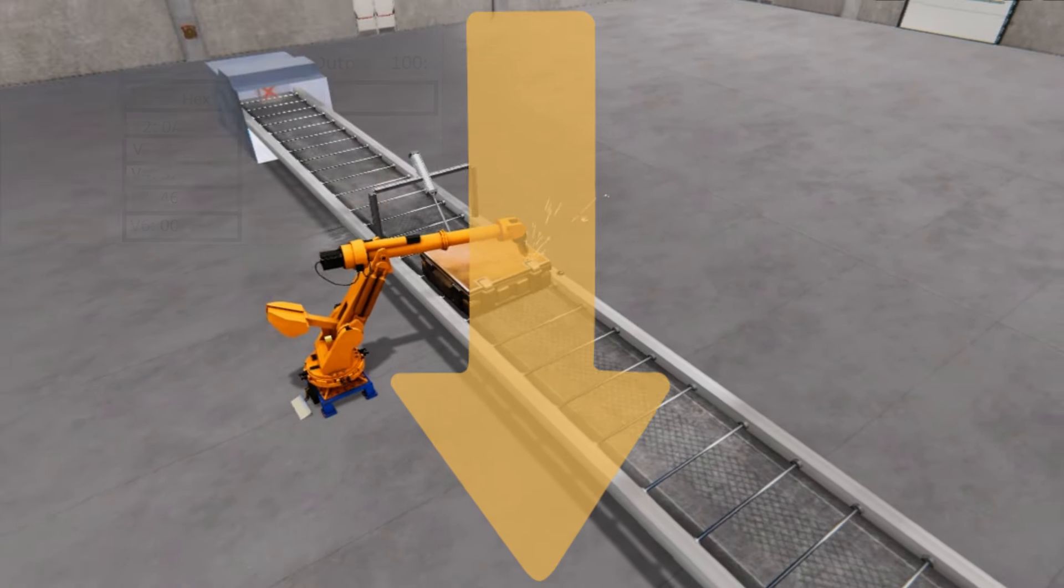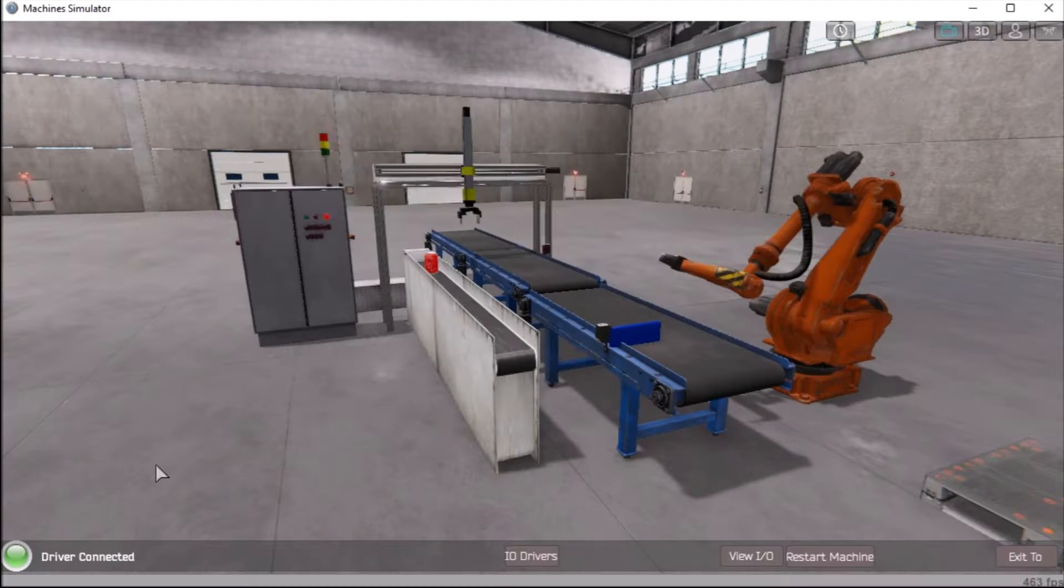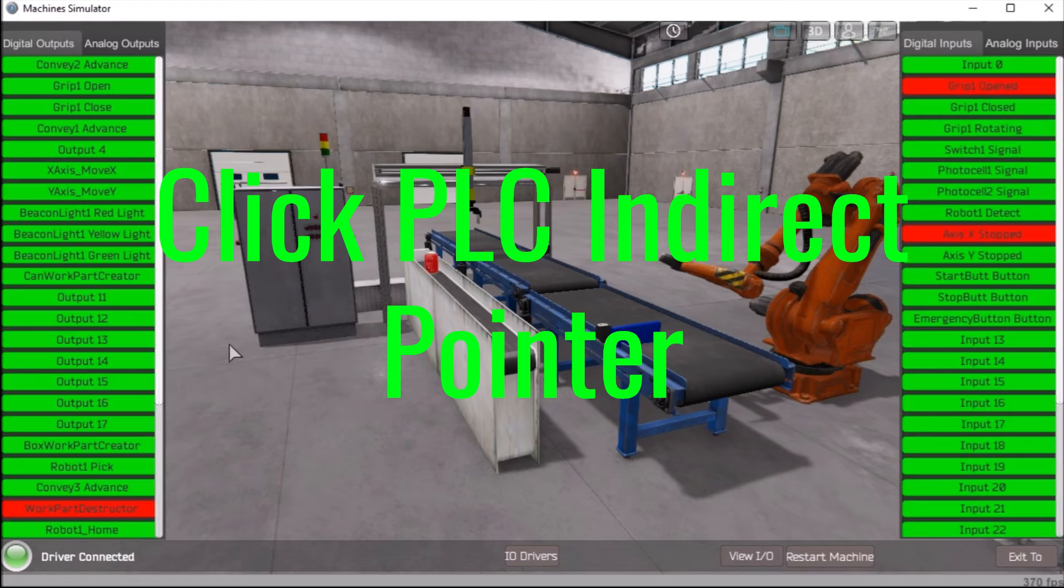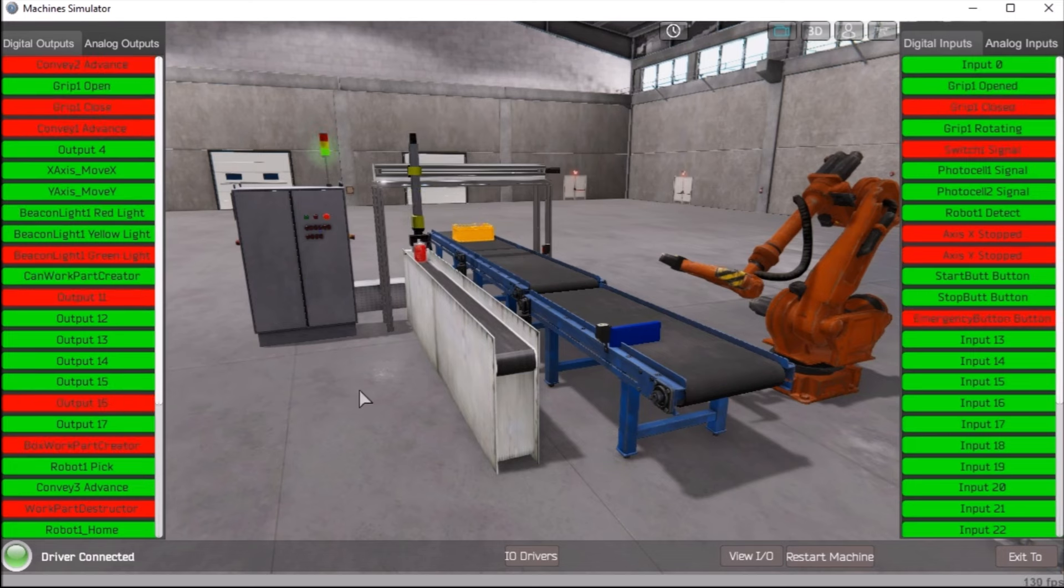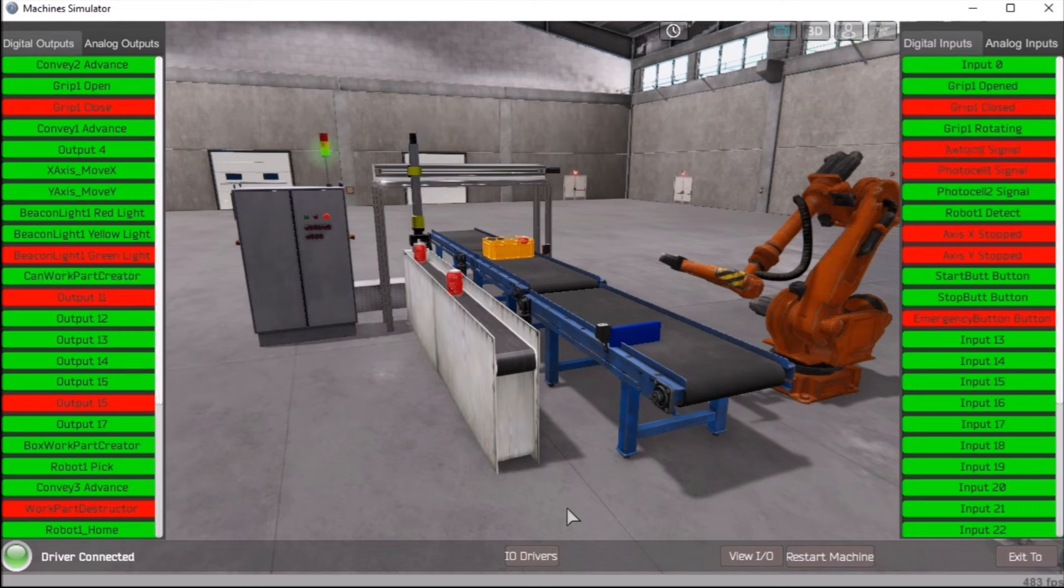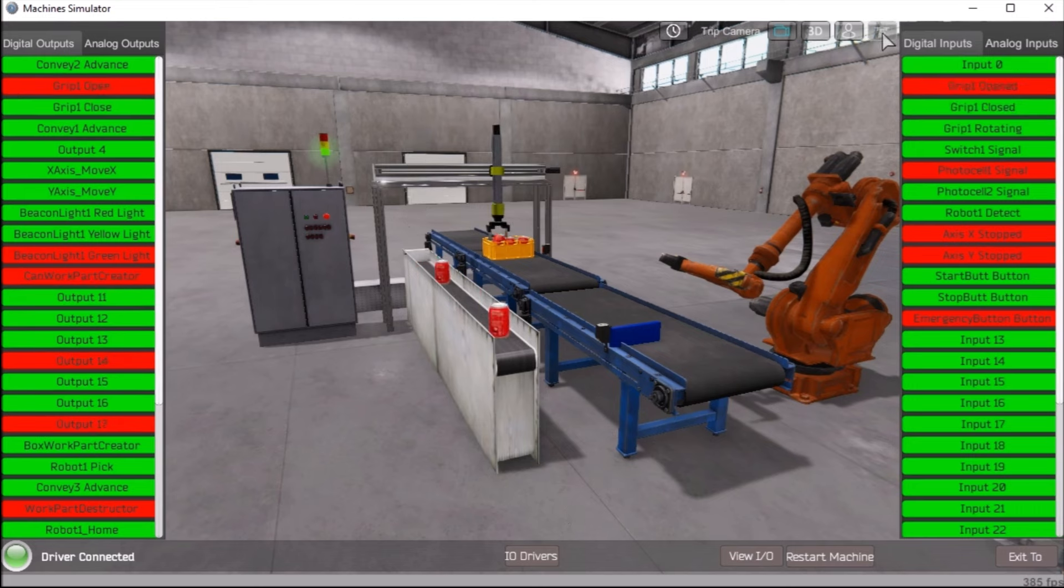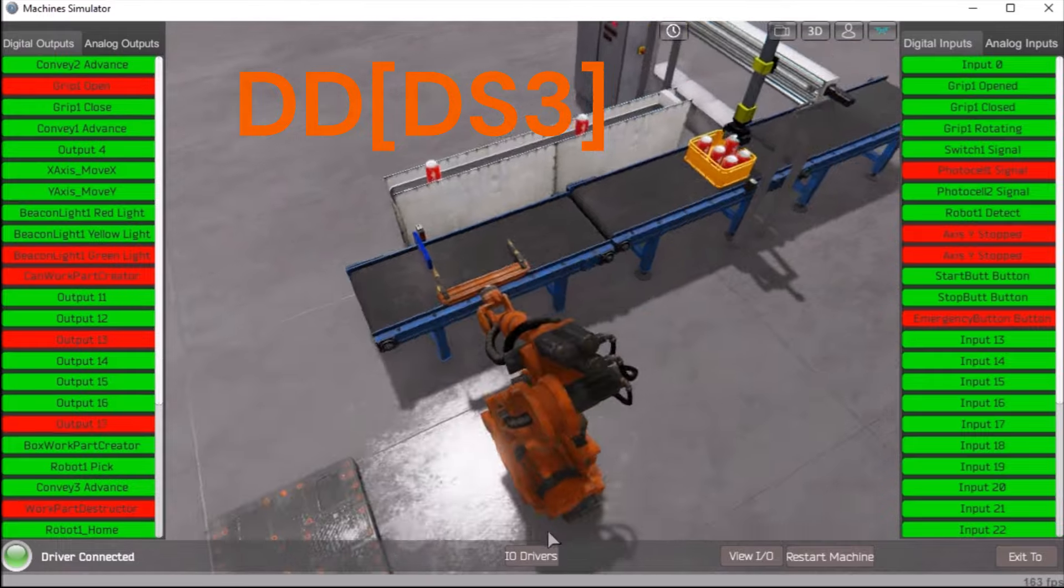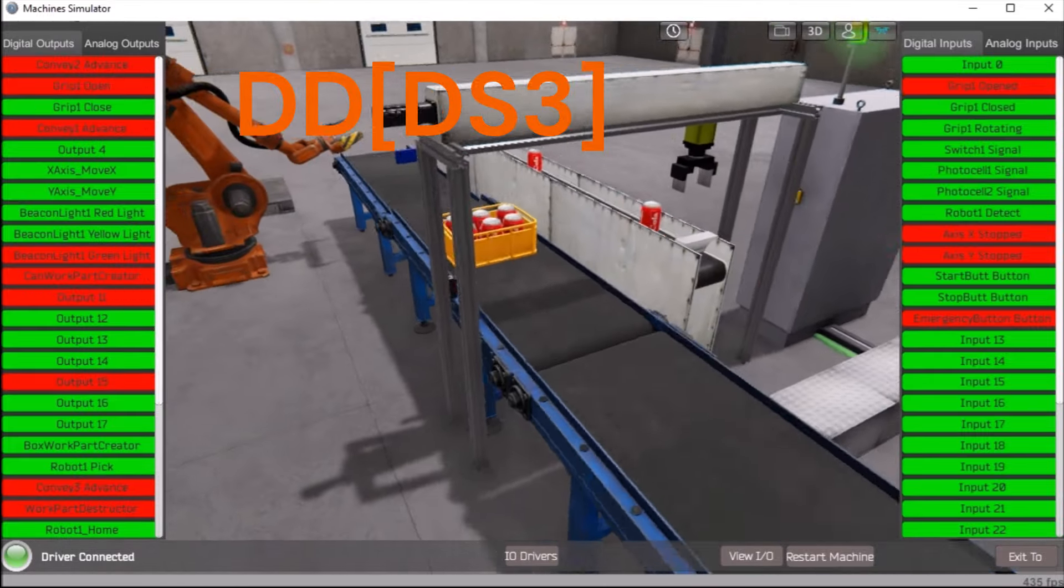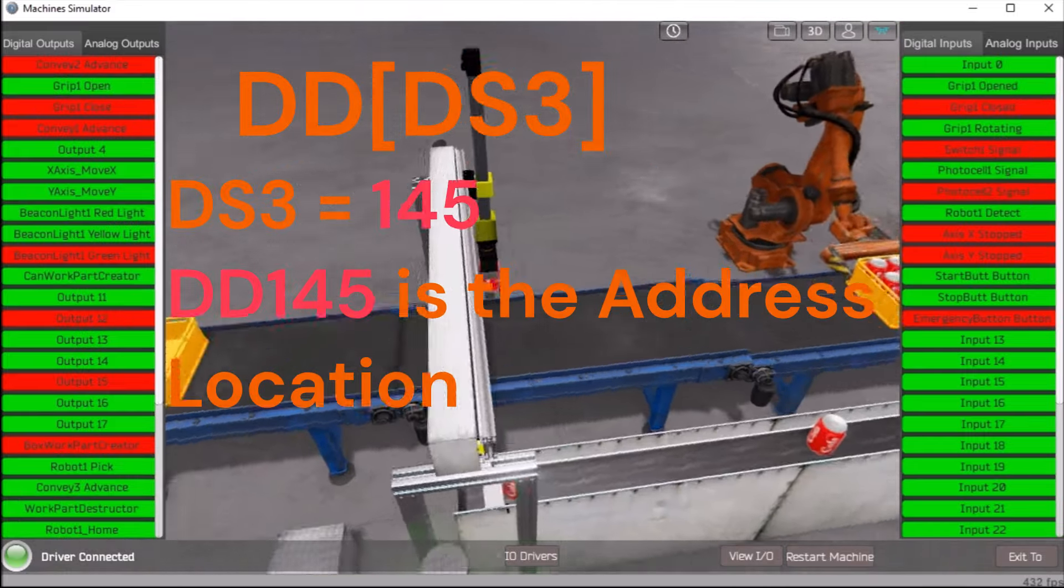Click PLC Indirect Pointer. The Click PLC supports indirect addressing, which the manuals refer to as pointer addressing. This method utilizes the DS as the offset value and can be used with the DS, DD, DF, DH, XD, YD, TD, CTD, and TXT data register memory types. Example: DD[DS3]. This will point to the address in DD that the DS3 value contains. If DS3 has a 145 value, the address will use DD145.